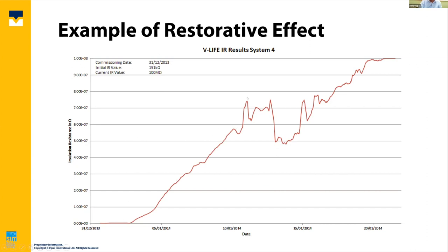Now, these peaks and troughs are absolutely normal, and it's part of the algorithms within V-Life and the correction as it's seeing what the effect of applying the signal is doing, it's self-correcting. So for instance, here, it took some time for that drop to be corrected and then different signals applied to continue the upward trend. This is typical. We don't always achieve 100 mega ohms. Sometimes it'll get up to 500 mega ohms. Sometimes it'll get up to 50 mega ohms. It all depends on the actual failure mode that we're trying to correct.